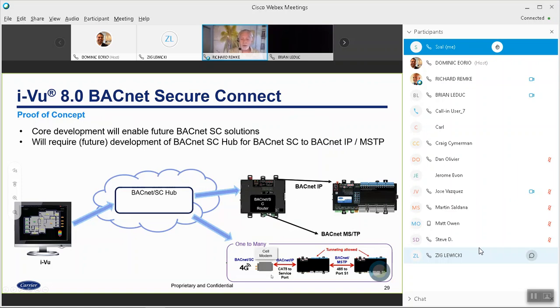Another thing we're looking at doing is using cell modems. So for job sites where you have no on-site front end, or for things where you may only be interested in the carrier equipment, maybe a chiller or a rooftop, and there's already some other BMS on site, but for warranty purposes or service purposes, you want to be able to connect to it. You'll be able to use the BACnet Secure Connect scenario with that. We're actually looking at putting BACnet Secure Connect into a cell modem. And then it'll be standard BACnet IP throughout the site.